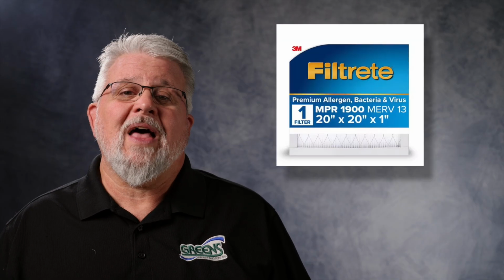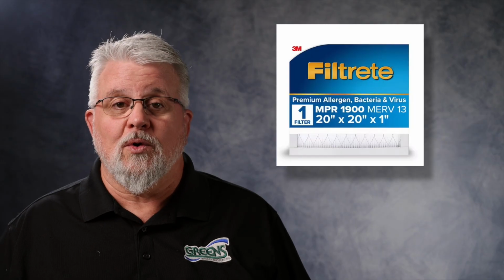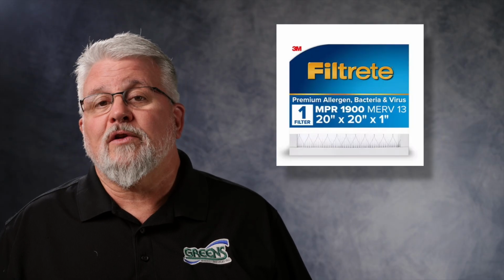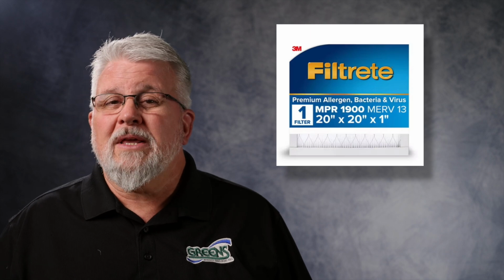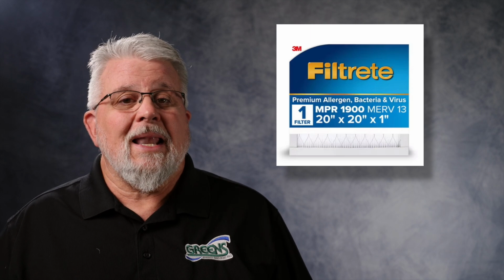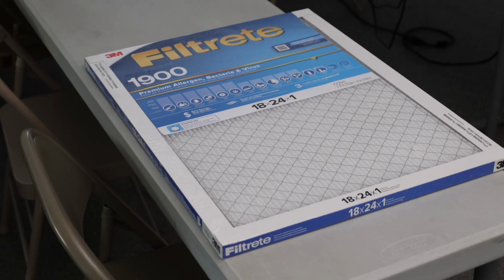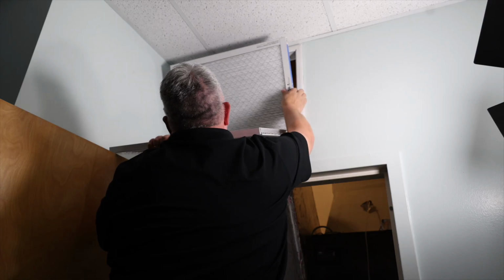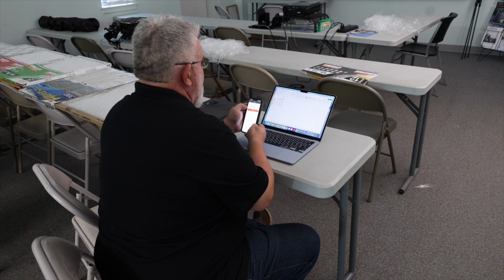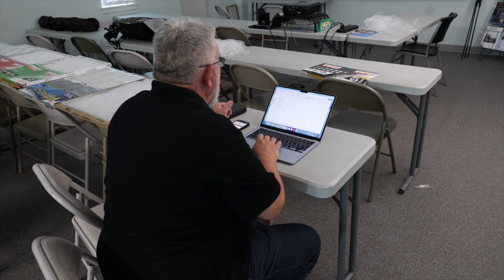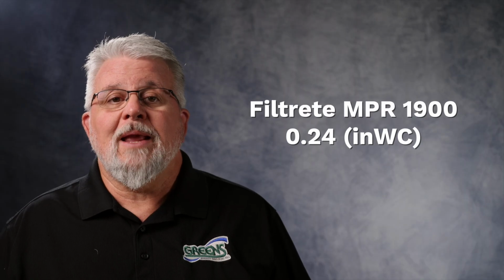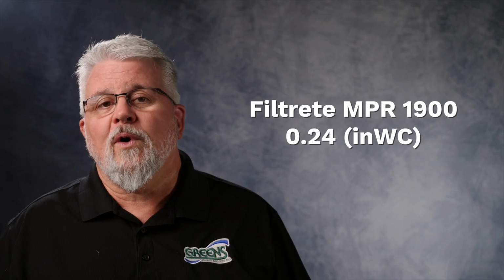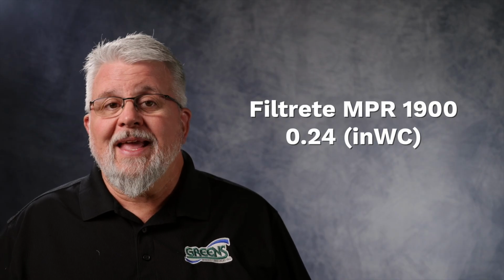And finally, we tested the Filtrete 1900. This was the highest rated Filtrete filter I could find locally, and honestly, after seeing the results from the 1500, I was extremely curious how this one would perform. Like the 1500, it uses a very dense pleat design with a tremendous amount of surface area, and once again, the results surprised me. This MERV 13 filter produced a pressure drop of just 0.24 inches. That's dramatically lower than the HDX MERV 13 filter we just tested.